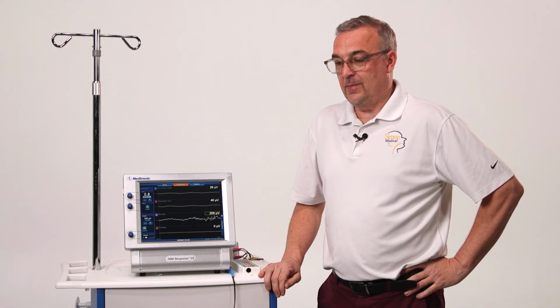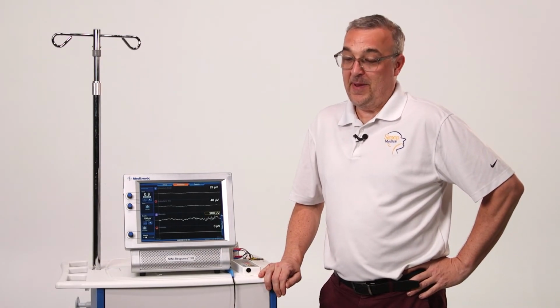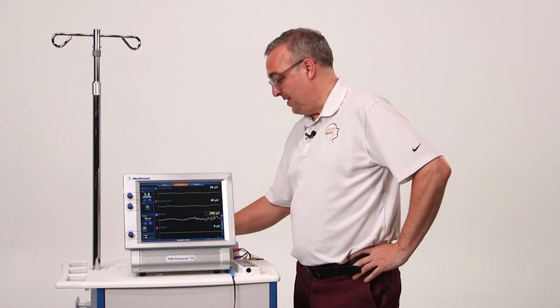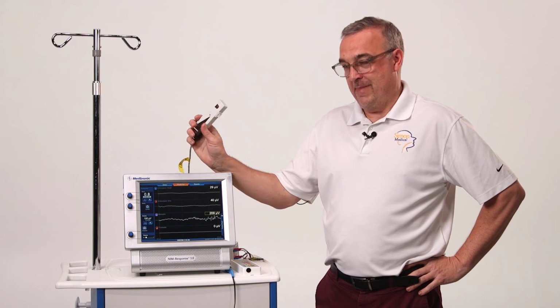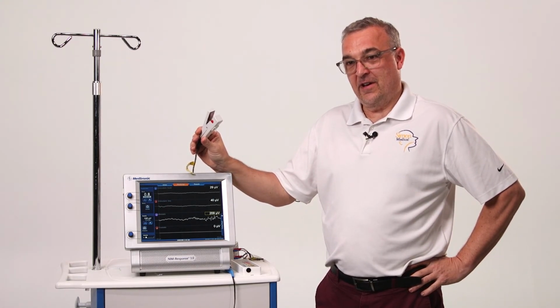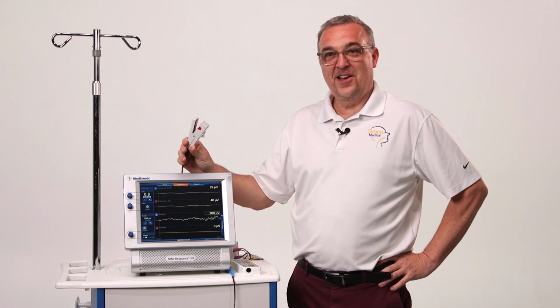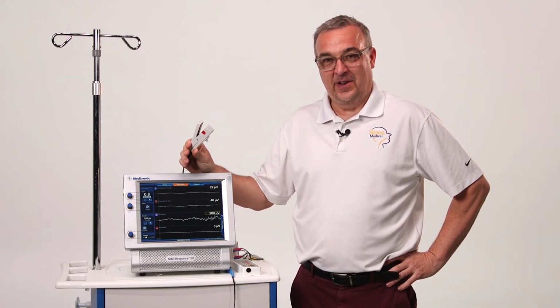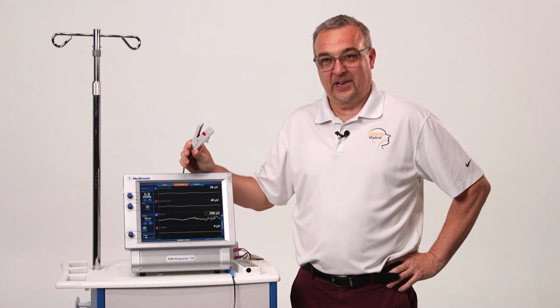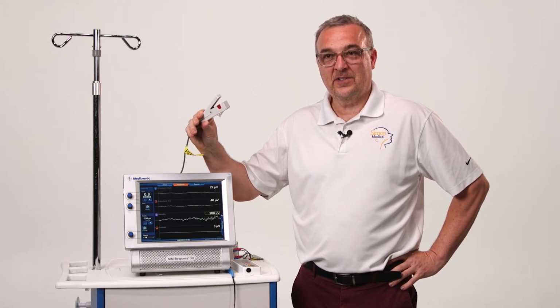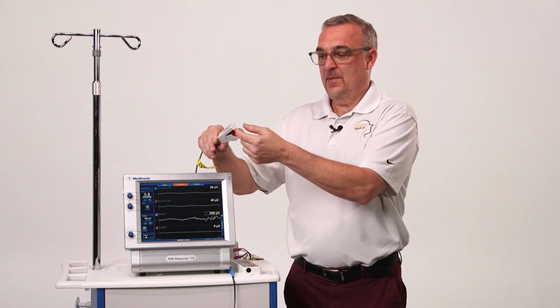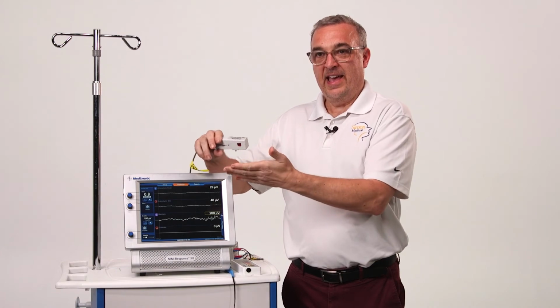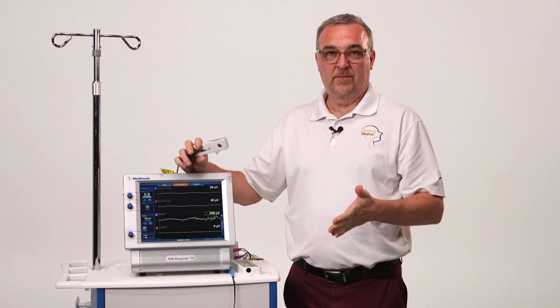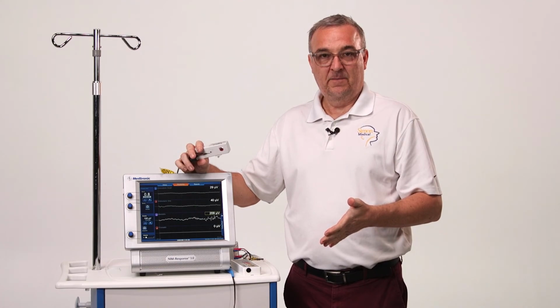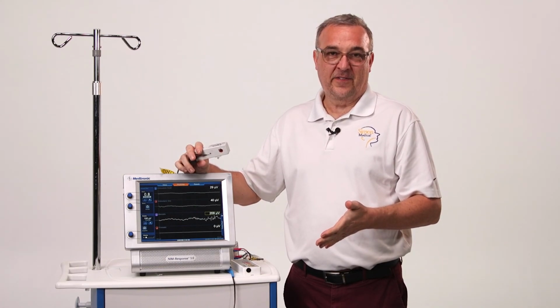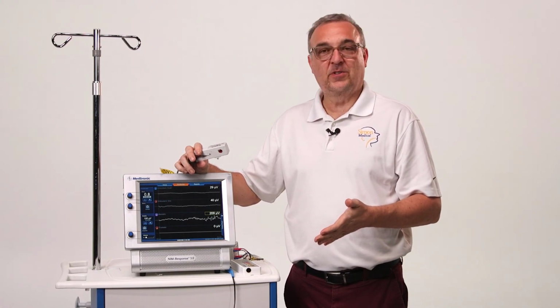One additional troubleshooting topic, and maybe one of the most important: if you forget to put the muting cable on the monopolar lead that's coming out of the electrocautery box, you're going to get a lot of artifact. So if you're getting a lot of noise and a lot of artifact, especially when electrocautery goes off, check to make sure this is hooked up. Take the monopolar lead, put it in here, clamp it, you can wrap it around, have it very up close to the box, and it will mute the nerve monitor when electrocautery is being used. So that's another common thing that I've seen that I thought we should interject.